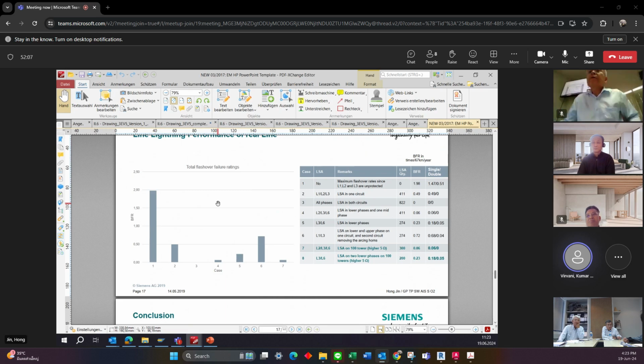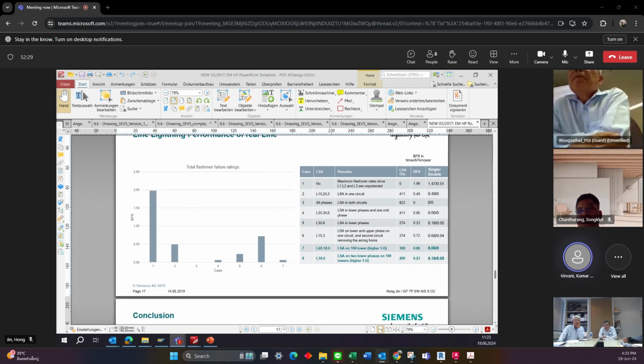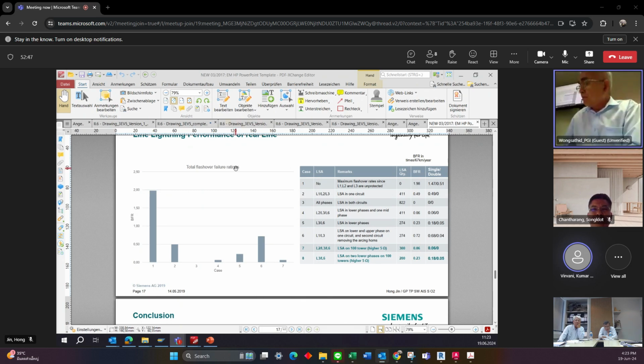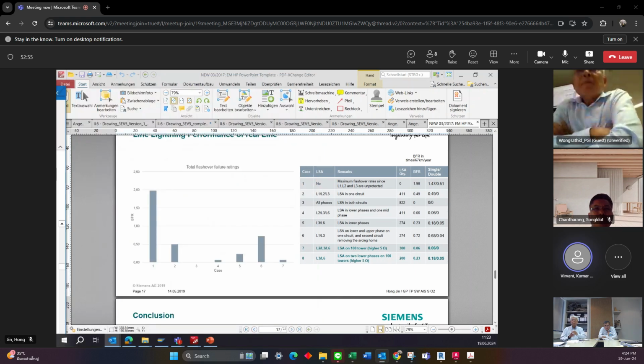Hi everyone, this is Kumar this side. I also want to add some input on the line study. Until now, I have done multiple line studies for different systems, in different countries and different geographical locations of the transmission line. From that experience I understand that whenever I perform that study I get a very different result each time, because the line study depends on the inputs we give to the system. Like we need the system data and the geometrical data of the conductor, the span between two towers, and it also varies based on the tower footing resistance.